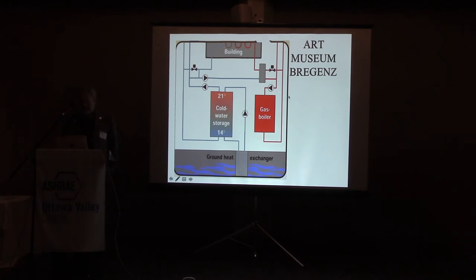At that time, we didn't use so many heat pumps, so it was a condensing gas boiler that did the heating. But the cooling was made by a ground source heat exchanger, and no chiller or heat pumps were involved, because pipes were embedded also in the foundation. By circulating down to the foundation with piping integrated here, we could have a storage tank with about 14 degrees, and that was enough to do the cooling. So the only cost for the cooling was really running the circulation pump.